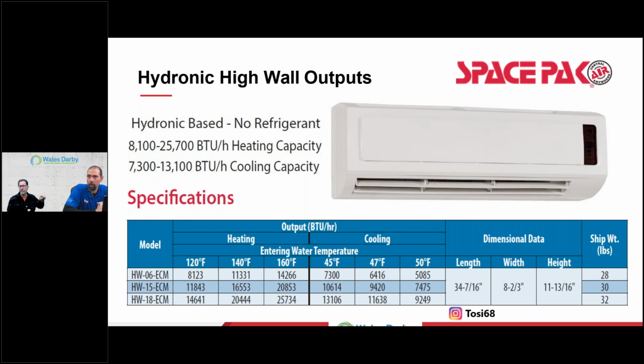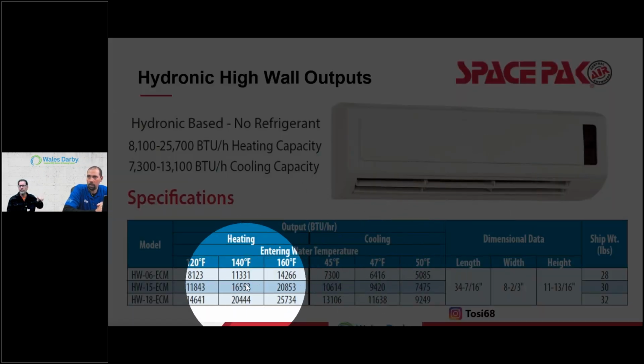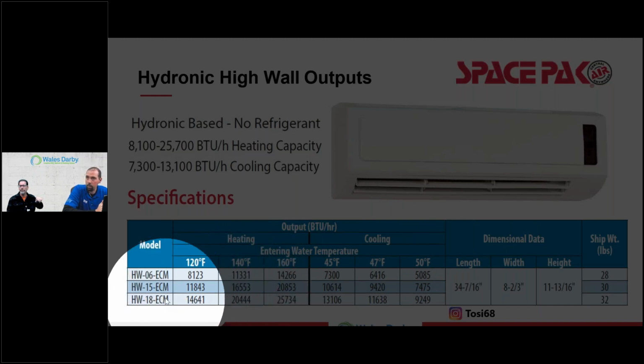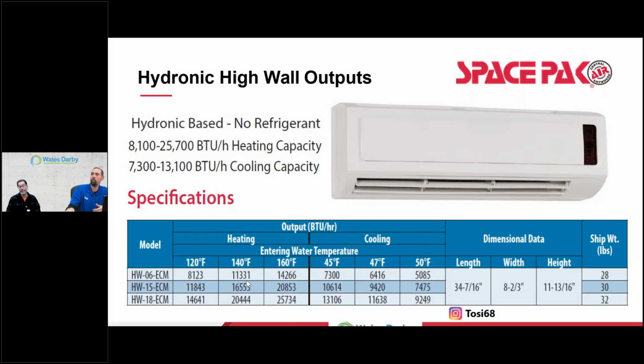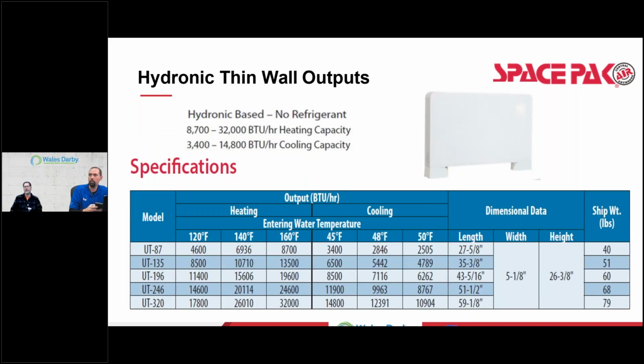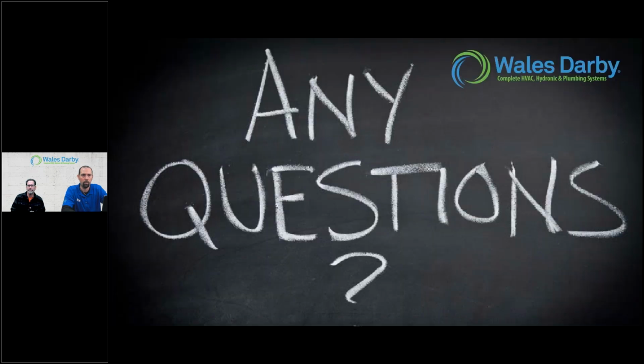So if you did 140 degrees of water on that HW15, the middle one there, at 140 degrees, so you get 16,553. Right. That's going to convert to about 28 feet of baseboard. So that's, you know, again, it's kind of neat to see. People don't want baseboard anymore. What can you offer, right? Well, how about something like this, right? So here's another thin wall. It's like a console, clear glass, nice display, you know, and they have different models here. Again, lowering water temperature, but high output BTUs. Well, wow, look at that.